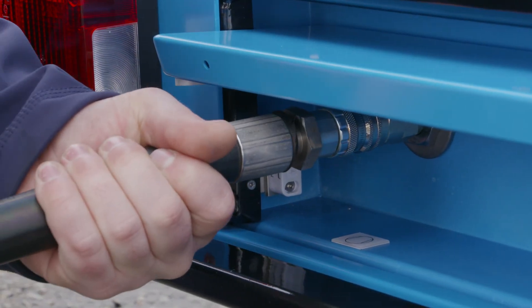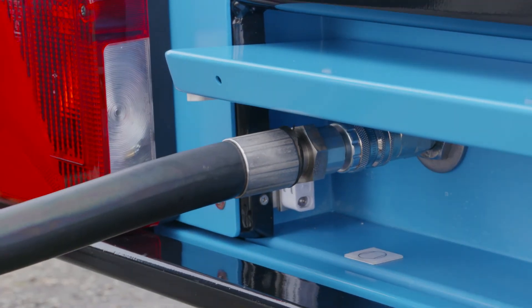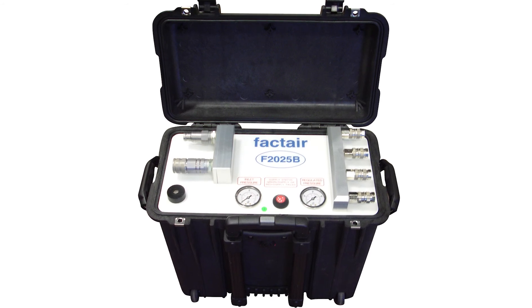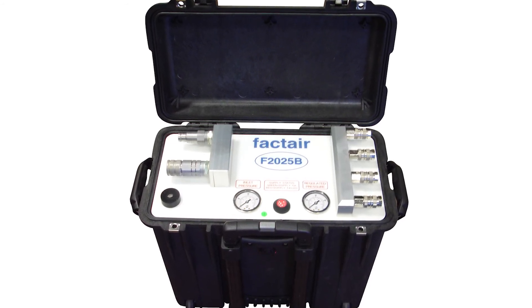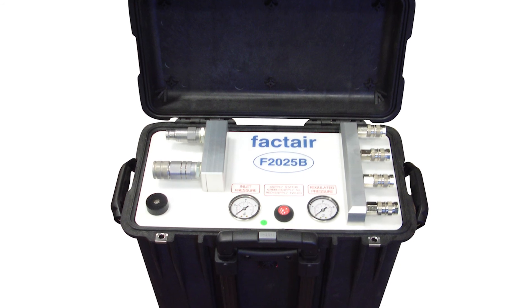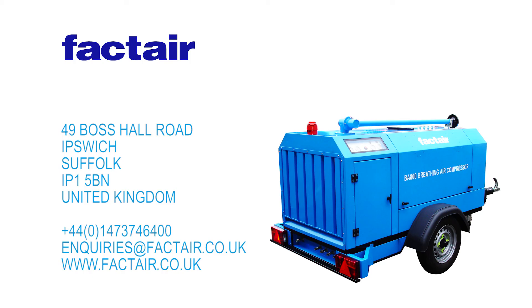This can be connected via a half or three-quarter-inch hose to the unregulated outlet and allows the total flow from the unit to be supplied through a single larger airline to your worksite. In the event of the BA800D switching over to its emergency reserve, the pneumatically controlled F2025 will automatically detect the changeover and sound a local alarm to warn users to withdraw to a place of safety. We hope that now we've shown you the safety features of the FACTAIR system, you will share our confidence that this equipment can form the basis of a safe system of work. If you have any questions, contact FACTAIR for more information and details of your local distributor or visit our website. Thank you for watching.